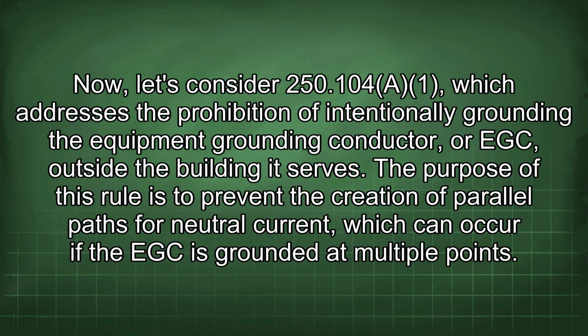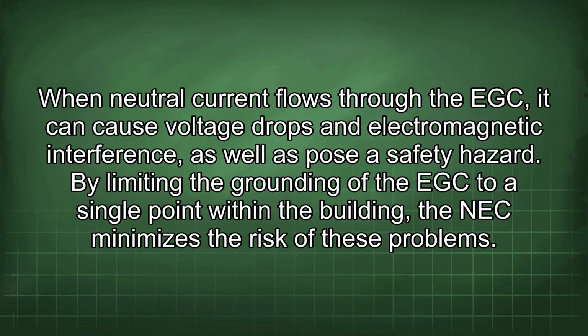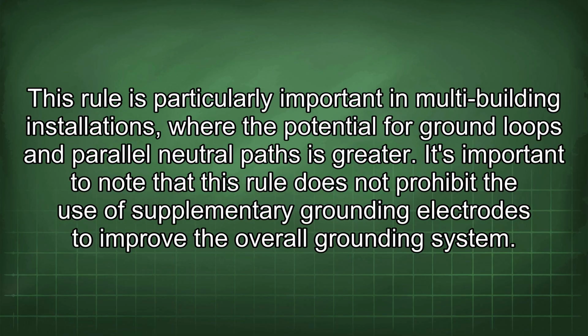Now, let's consider 250.104a, which addresses the prohibition of intentionally grounding the equipment grounding conductor, or EGC, outside the building it serves. The purpose of this rule is to prevent the creation of parallel paths for neutral current, which can occur if the EGC is grounded at multiple points. When neutral current flows through the EGC, it can cause voltage drops and electromagnetic interference, as well as pose a safety hazard. By limiting the grounding of the EGC to a single point within the building, the NEC minimizes the risk of these problems.